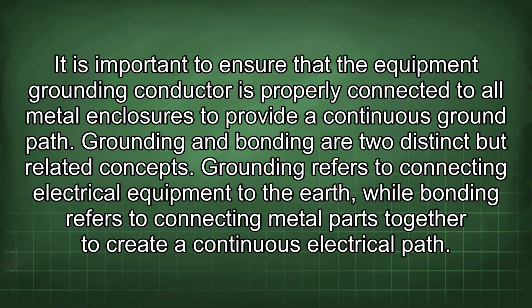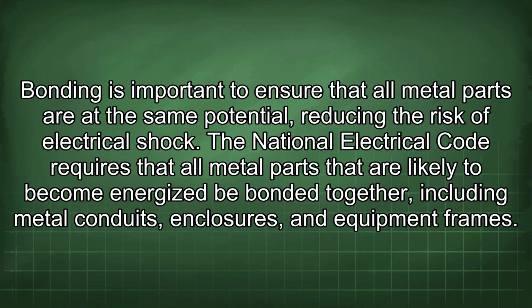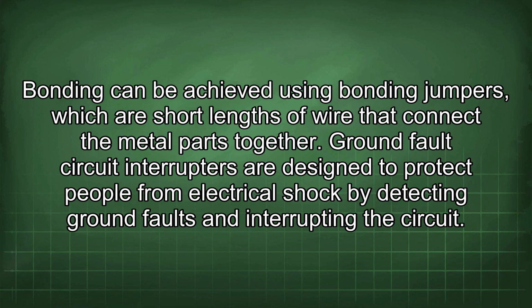Grounding and bonding are two distinct but related concepts. Grounding refers to connecting electrical equipment to the earth, while bonding refers to connecting metal parts together to create a continuous electrical path. Bonding is important to ensure that all metal parts are at the same potential, reducing the risk of electrical shock. The National Electrical Code requires that all metal parts that are likely to become energized be bonded together, including metal conduits, enclosures, and equipment frames. Bonding can be achieved using bonding jumpers, which are short lengths of wire that connect the metal parts together.